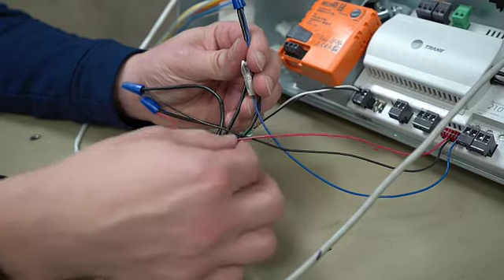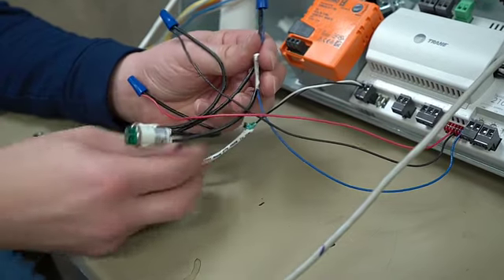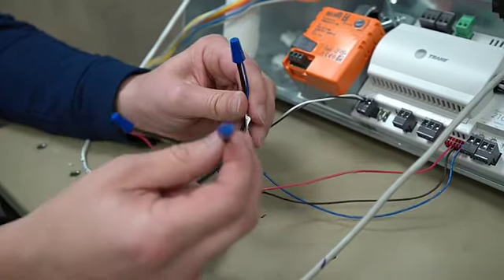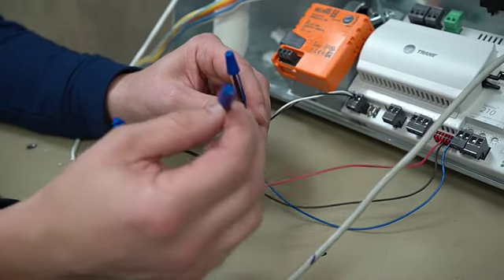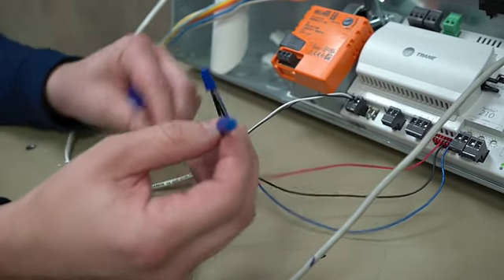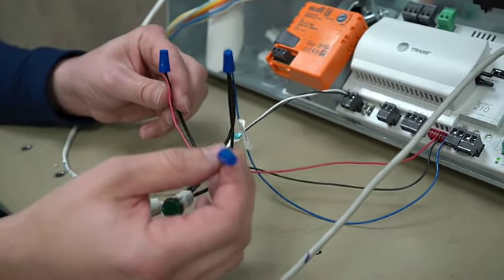So 24 volts is going on one side of this light bulb and then 24 volts is going on the other side of this light bulb. What I did was I took the open and close leg, so here's the open leg and then I have the closed leg, and it's going on the other side to complete the path here.